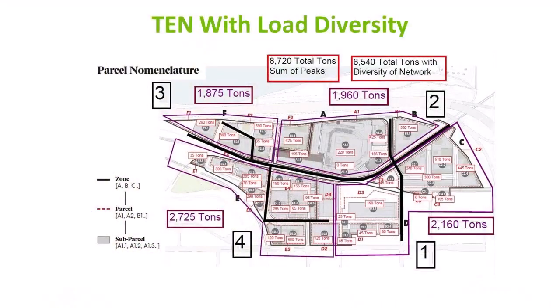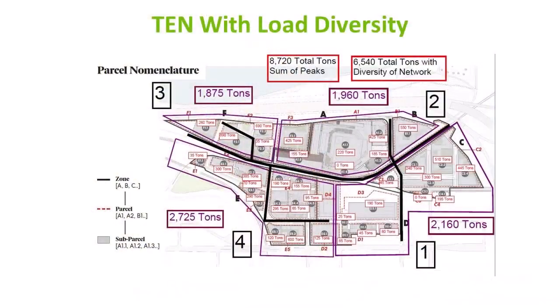If you took the sum of the peaks of the cooling load, we're almost 9,000 tons. But because we have a lot of buildings on the network with different occupancies, the diversified cooling load is just a little over 6,000 tons. That's a huge reduction in what we need to find to dump the heat off, just because of the variety of buildings on the thermal energy network.